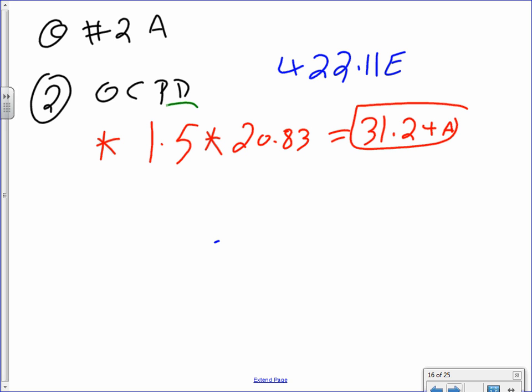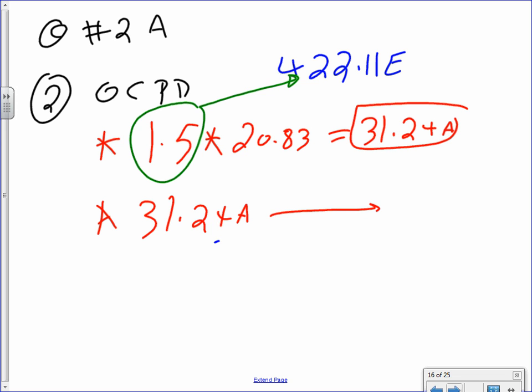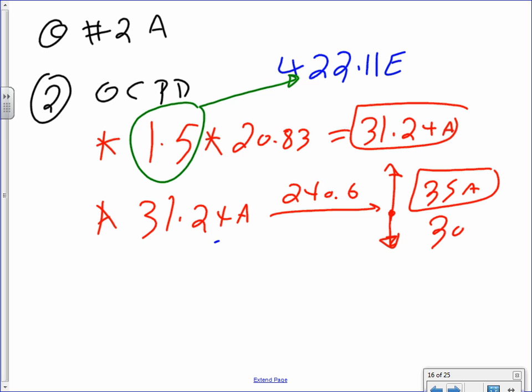Where did that number come from? This is directly from 422.11(E). Then you take the 31.24 and take it to 240.6. If it's not a standard size, you're allowed to go up to 35 amps, or you can go down to 30 amps. I want to put up and down, 35 amps or 30 amps, and I want to tell you which one we're going to use.